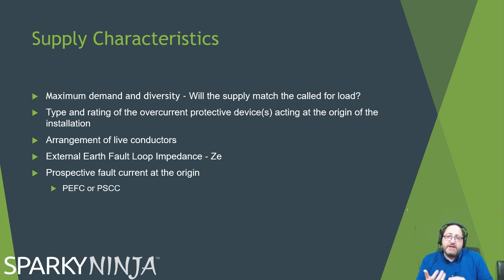So with supply characteristics, you've got maximum demand and diversity. Will the supply match the called for load? With regards to maximum demand and diversity, you've also got to consider thermal strains as well. Type and rating of the overcurrent protective device, arrangement of live conductors, external earth fault loop impedance, and the prospective fault current. These are all supply characteristics, and your knowledge of them is important. You may be asked which supply characteristic can be obtained by measurement. Well, that's clearly going to be either your Ze or your PFC. You're not going to measure an arrangement of live conductors, for example.